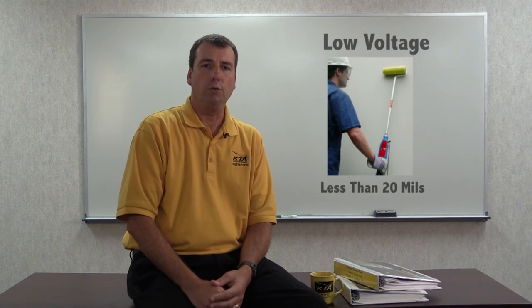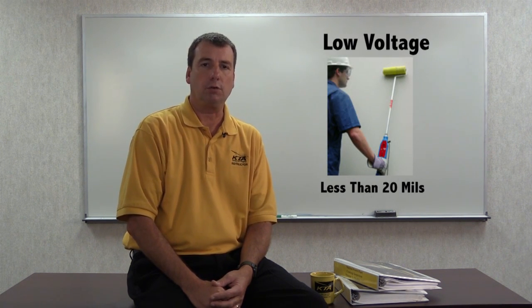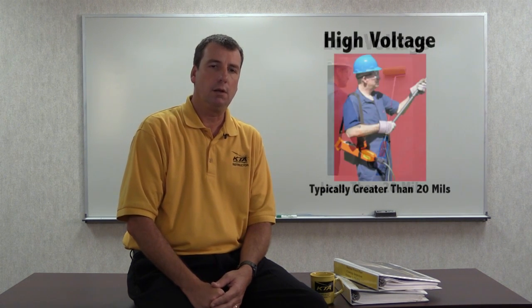There are two different types of holiday detectors. The one you select is based on the total thickness of the coating or lining system. Low voltage or wet sponge holiday detectors are used on coatings and linings that are less than 20 mils thick. High voltage holiday detectors or spark testers are used on coatings and linings greater than 20 mils thick and in some cases down to 10 mils.